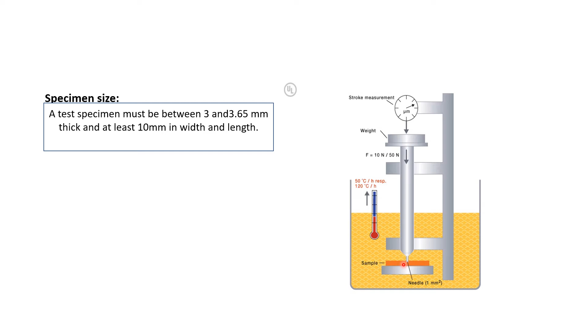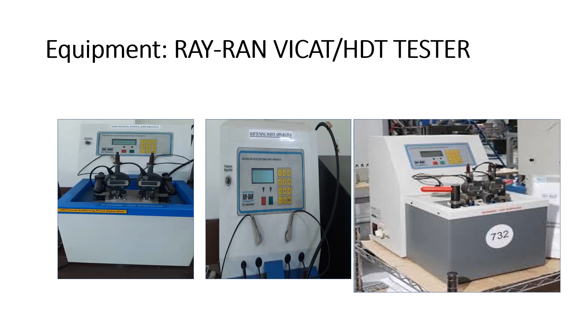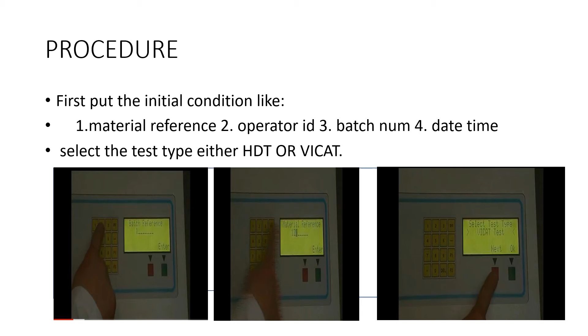The equipment which is used in the research lab to calculate the Vicat softening temperature and heat distortion temperature of the polymer is the Ray-Ran Vicat HDT tester. That is the procedure to calculate the Vicat softening temperature and HDT by the Ray-Ran Vicat HDT equipment. First of all, we put in the initial conditions on the screen: operator, material reference, ID, batch number, date and time, as you can see in that picture. Then we select the type we want to proceed with, which is either HDT, which stands for heat distortion temperature, or softening temperature. Then we press OK and proceed further.